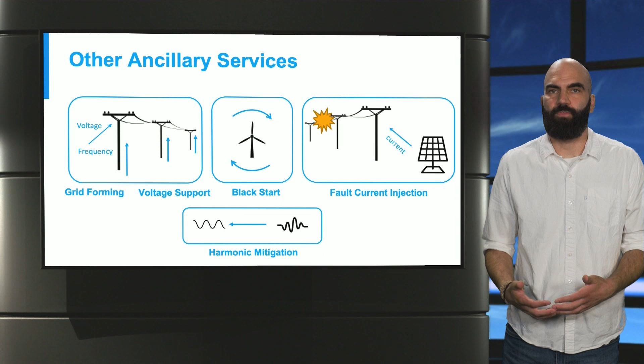Grid forming, black start, fault current injection, and harmonic mitigation are the final four types of services, each directed at a different need of the grid with a high percentage of wind and solar resources. Grid forming services refer to the ability to dictate grid frequency and voltage. Black start services refer to the capability of starting up power plants in a grid with no electricity. Fault current injection services are used to overcome challenges with the protection system, which arise as a consequence of replacing conventional sources with renewable sources. Finally, harmonic mitigation services refer to active harmonic filtering by power electronically interfaced sources.